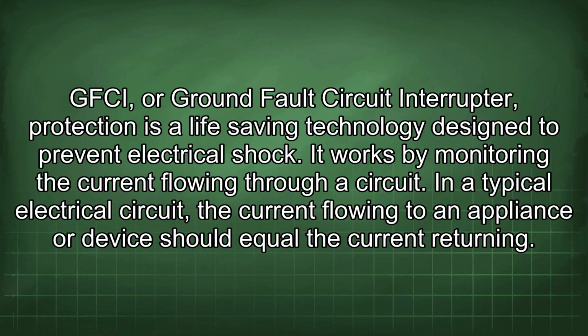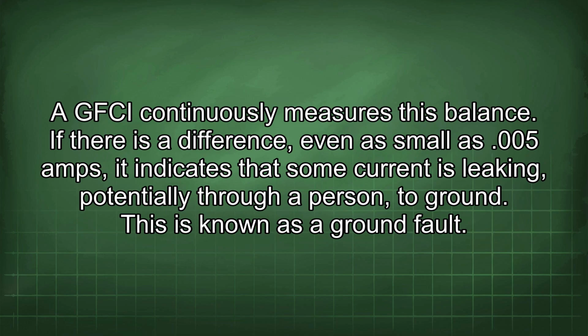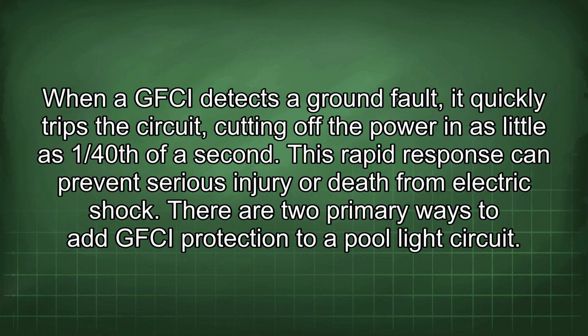GFCI, or ground fault circuit interrupter, protection is a life-saving technology designed to prevent electrical shock. It works by monitoring the current flowing through a circuit. In a typical electrical circuit, the current flowing to an appliance or device should equal the current returning. A GFCI continuously measures this balance. If there is a difference, even as small as .005 amps, it indicates that some current is leaking, potentially through a person to ground. This is known as a ground fault. When a GFCI detects a ground fault, it quickly trips the circuit, cutting off the power in as little as 1/40th of a second. This rapid response can prevent serious injury or death from electric shock.